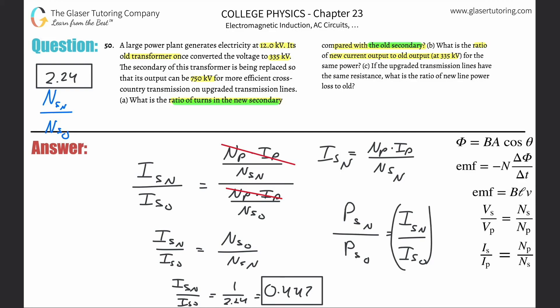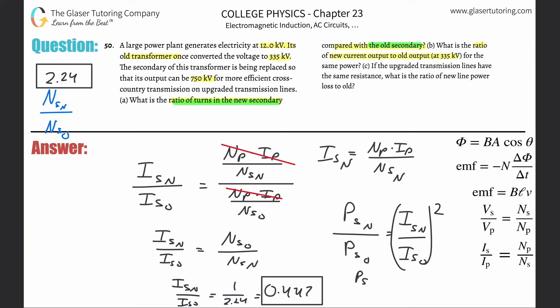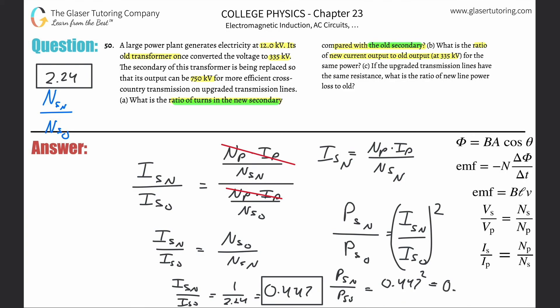We can square the current ratio we just calculated. So we take 0.447 and square it: 0.447 squared equals approximately 0.200. Rounding, you get about 0.200. That's the ratio of the new power line loss to the old — the upgraded line loses only about 20% of what the old line lost.